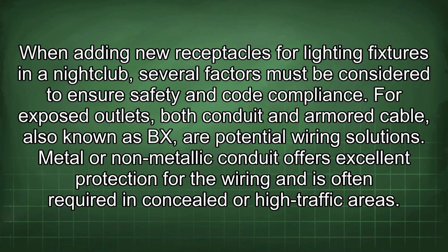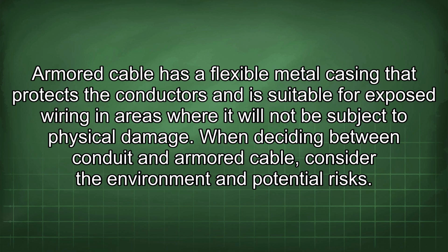When adding new receptacles for lighting fixtures in a nightclub, several factors must be considered to ensure safety and code compliance. For exposed outlets, both conduit and armored cable, also known as BX, are potential wiring solutions. Metal or non-metallic conduit offers excellent protection for the wiring and is often required in concealed or high-traffic areas. Armored cable has a flexible metal casing that protects the conductors and is suitable for exposed wiring in areas where it will not be subject to physical damage.